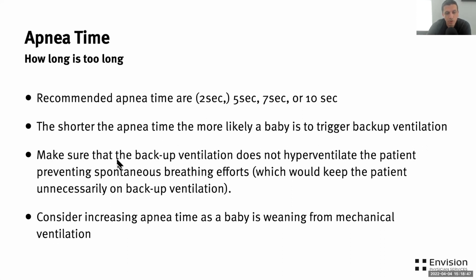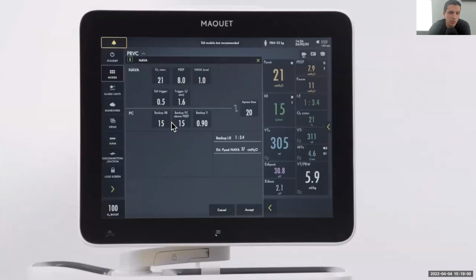Now you have to make sure too that the backup ventilation settings you're putting on the vent are not too generous because you don't want to hyperventilate the infant. So when we go back to this picture, we see here the bottom 3 squares are your backup ventilation. This is the backup respiratory rate, set here as 15. You have your backup PC above PEEP, which is your PIP, and your backup I time. And this here is your apnea time. I think this is for an adult, obviously. So they set it at 20 seconds, but I wouldn't set it to 20 seconds, as I said, between 5, 7, or 10 seconds.